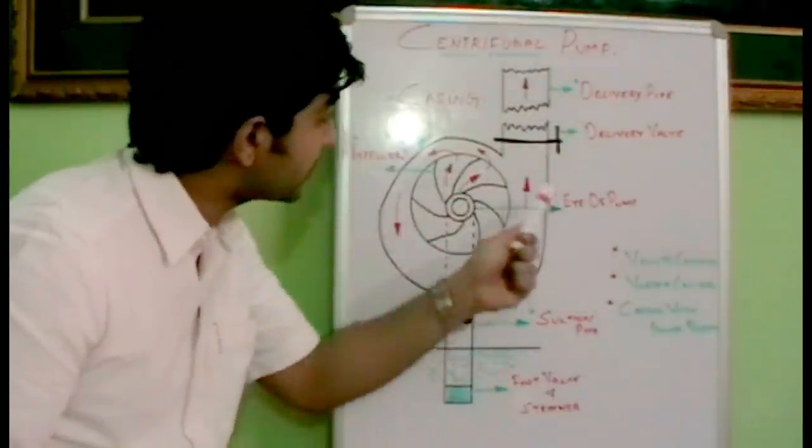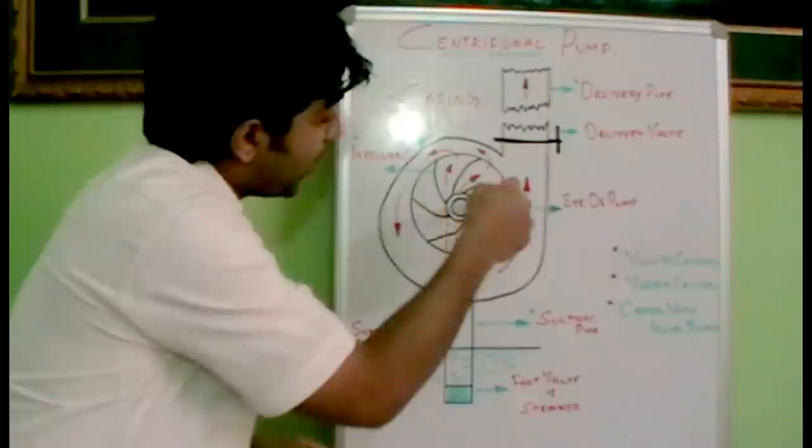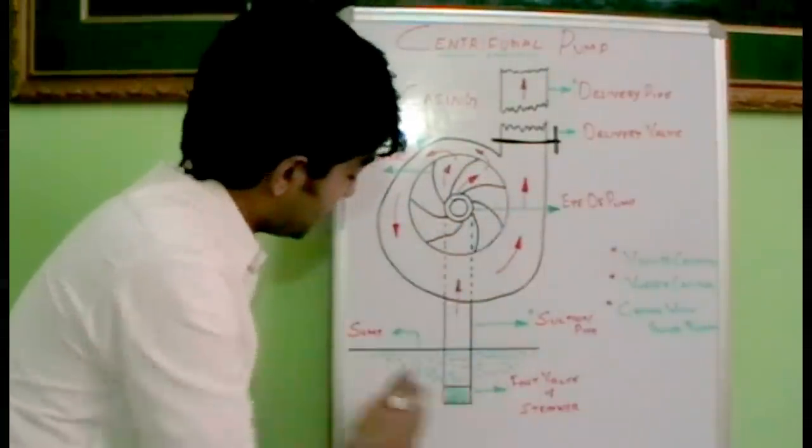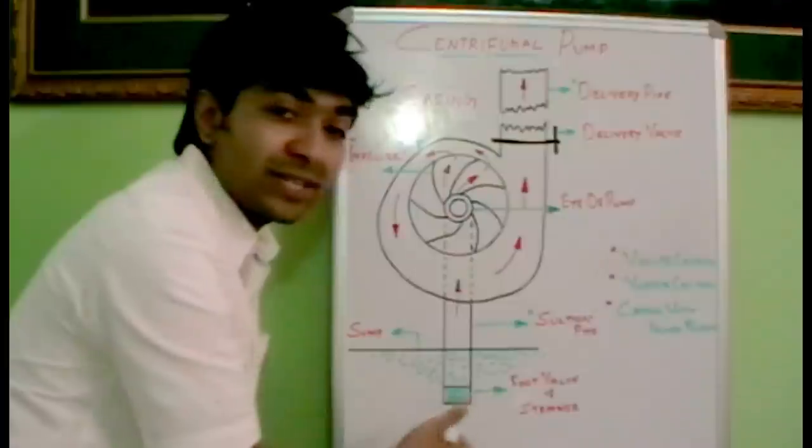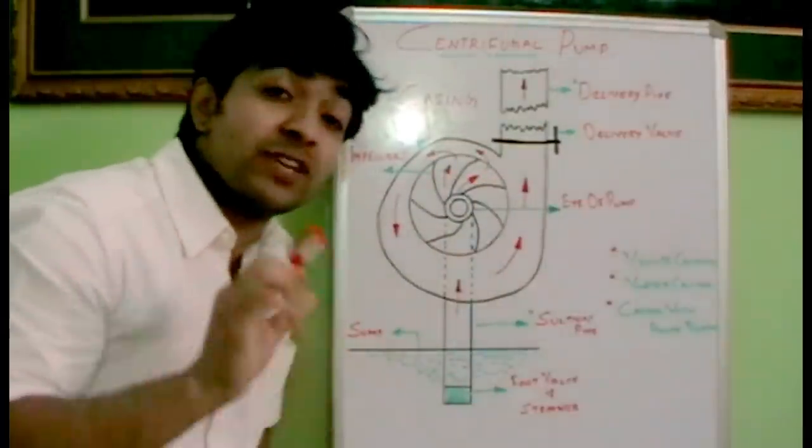This is the casing which is one part of the centrifugal pump. And the other is the impeller with the vanes over here, the center one, the heart of the centrifugal pump. And we have a suction pipe which is immersed towards the sump with foot valve and strainer and the delivery pipe. These are the four main components of a centrifugal pump.